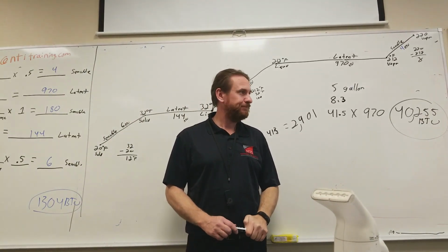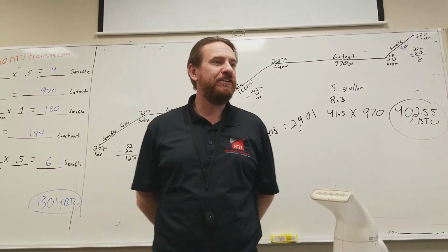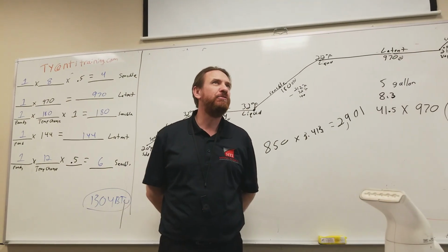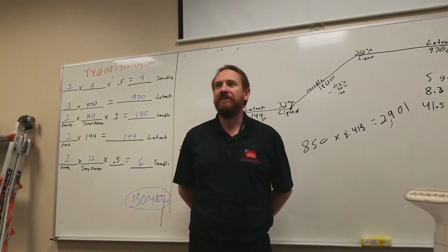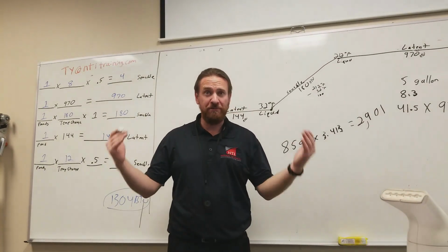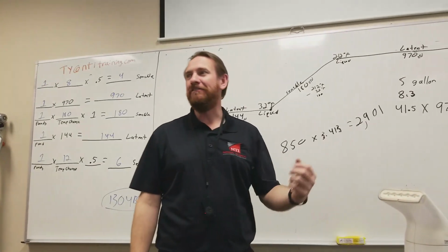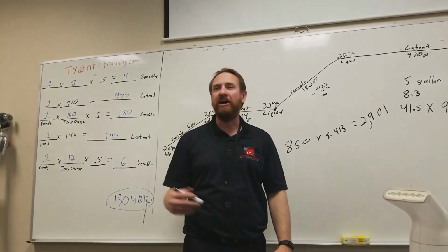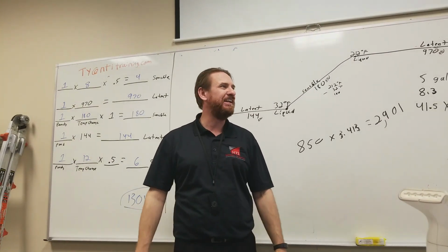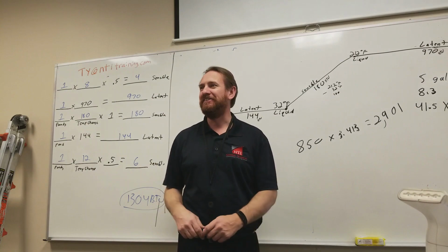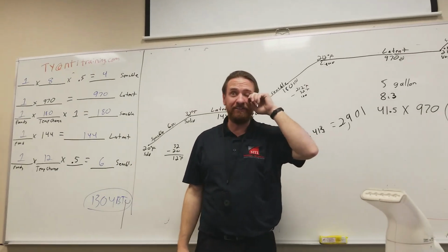An air conditioner here is going to be much more efficient than the exact same air conditioner in Florida. Not necessarily efficient, but you have a different difference of what it's moving. Here, you're changing mainly sensible heat of the air. So a lot of the air conditioners here very seldom have any moisture coming out of them because your humidity here is so low already. But in Florida, the humidity is much, much higher, so you need to dehumidify. So in Florida, there's water coming out of that drain constantly. Here, sometimes people never even see water coming out of their air conditioner until that one day that it rains and the humidity goes up and your AC starts to dehumidify, and they're like, oh, why is there water coming out? But it's because of the latent heat capacity of it.